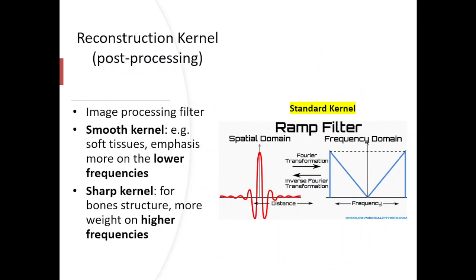Finally, the reconstruction kernel. Reconstruction kernels apply filters to enhance different structures in the image. A smooth kernel is used for soft tissues, while a sharp kernel enhances edges, making it ideal for bone scans. Most CT reconstructions use a standard kernel, which is equivalent to a ramp filter in filtered back projection reconstruction. Adjustments to enhance either the low or high frequencies can refine image details. The ramp filter in the frequency domain has higher weight on higher frequencies, and by adjusting its shape, it can correspond to a smoother or sharper kernel.